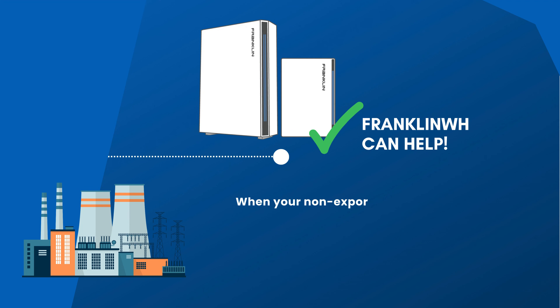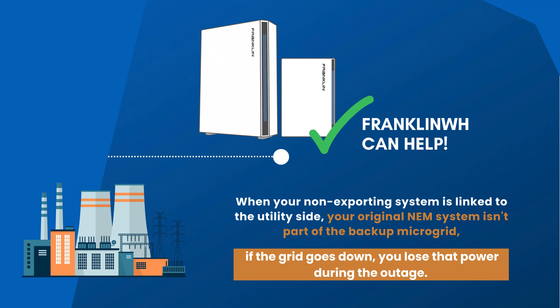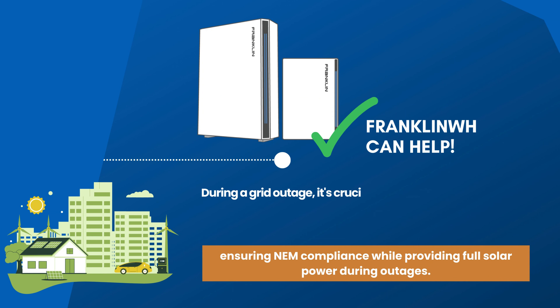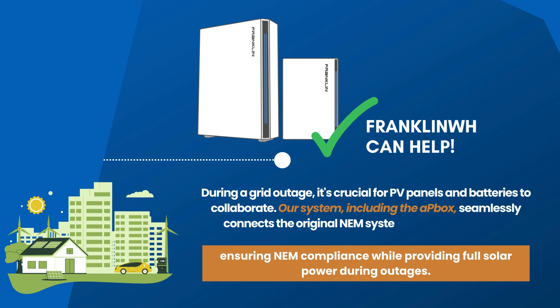That's a big deal because when you've got that non-exporting system and your original NEM system is connected on the utility side of the service interconnection, when the grid goes down, that original NEM system is not part of your backup microgrid. You want all of the PV on your roof and the batteries to work together. What we've enabled through our system — through the AP box — is interconnecting that original NEM system onto the loads panel, staying compliant with the updated regulations, but enabling that original system to work in backup mode too.